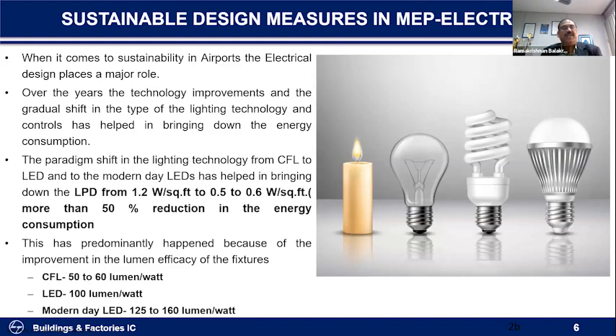Another major aspect is lighting in airports. The lighting power density used to be 1.2 watts per square foot with CFL lamps, but nowadays LED is popular, reducing energy by more than 50 to 60%. Even within LED technology there's improvement—modern lights achieve 160 lumens per watt, meaning even at lower wattage you get more light output. So when designing airports, look into these technical and specification aspects to get maximum benefit from the right materials and LEDs.